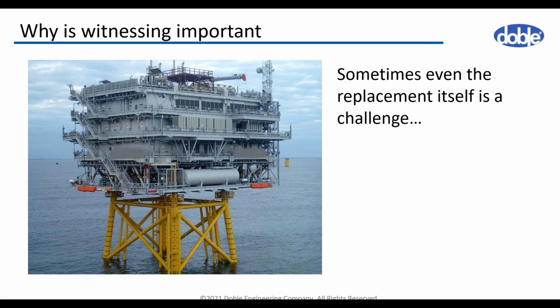So as I already mentioned, it's important to find all the problems within the factory when the unit is in the factory, because in some cases, just taking the transformer out of the site is very, very complicated and cost ineffective. So in this case, we have a platform here, and the transformer failed just after a couple of years and needed to be replaced. The process of taking the transformer out and replacing it with a new one is a very difficult one, and related with a lot of problems.